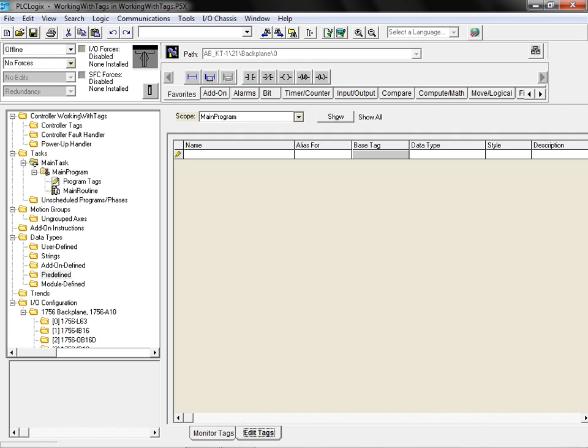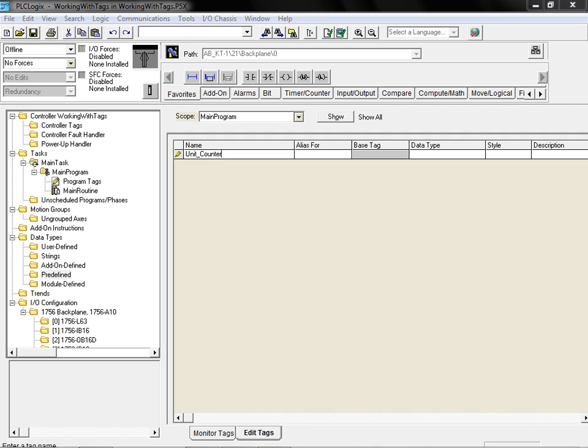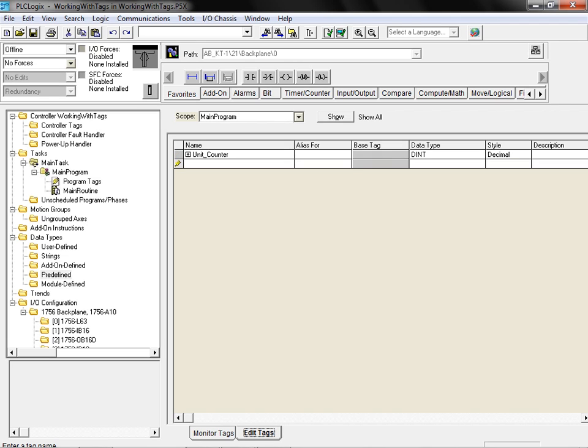Any tags created in this area will be limited in scope. They will only be available inside the main program. To create a new tag for the counter in our application, we simply enter the desired tag name in the text box provided. We then click enter to create the tag. The newly created tag is assigned the double integer data type by default.